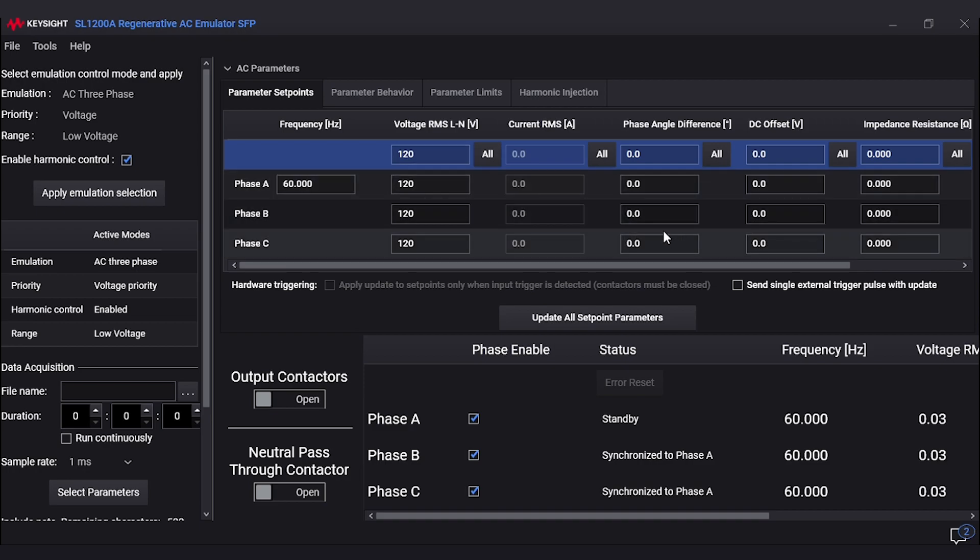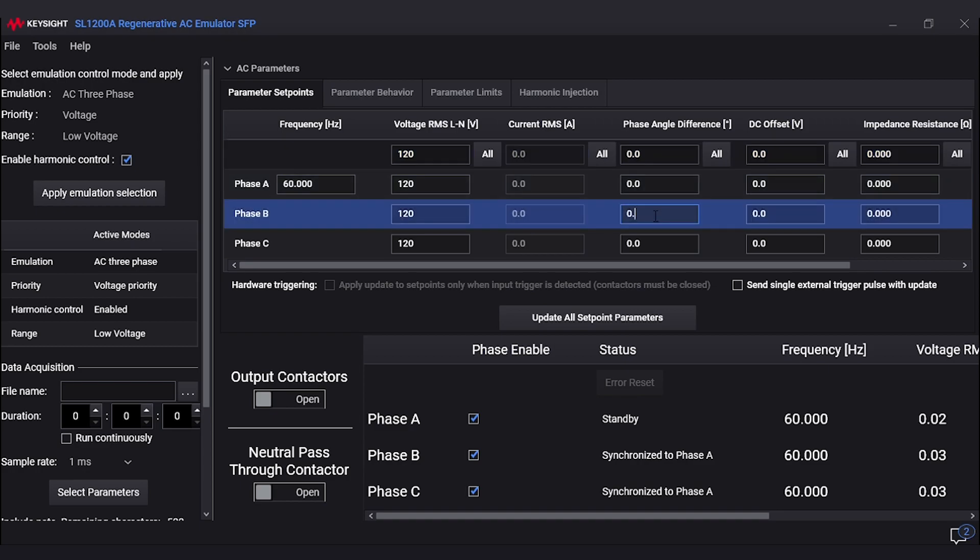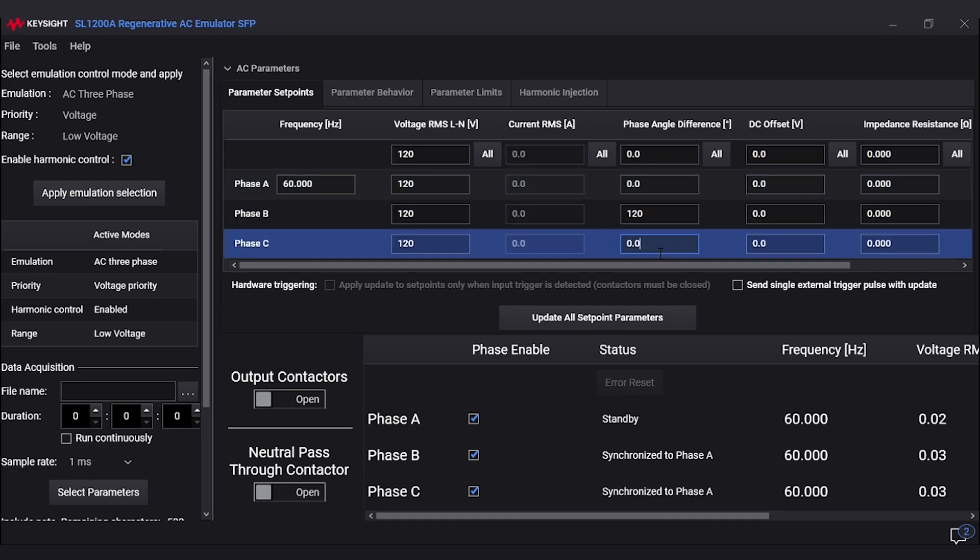The phase angle will also need to be inputted to the desired differences. Most typical differences are 120 degrees, so we'll be using 120-degree differences for phase B and 240 degrees for phase C.